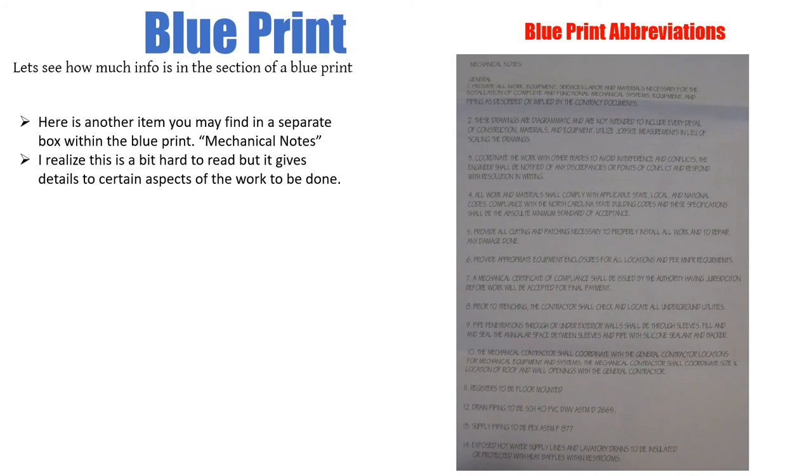So here's another item you may find in a separate box within a blueprint, some kind of a mechanical note. I realize that this is hard to read but it gives details to certain aspects of the work that has to be done. For our sake, if we just look down here for instance, number 12, drain piping to be Schedule 40 PVC piping DWV. It also shows us number 13, supply piping to be PEX. We even talked about DWV earlier in the very first slide. It stands for drains, wastes, and vents, so here's another place you may see an abbreviation pop up.